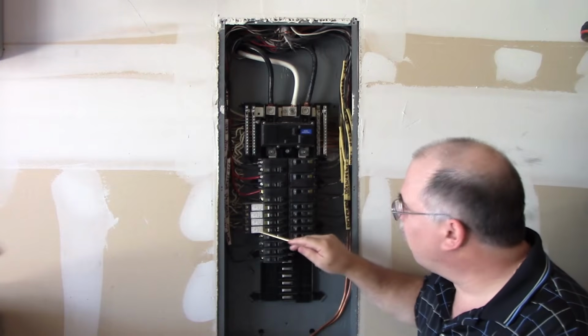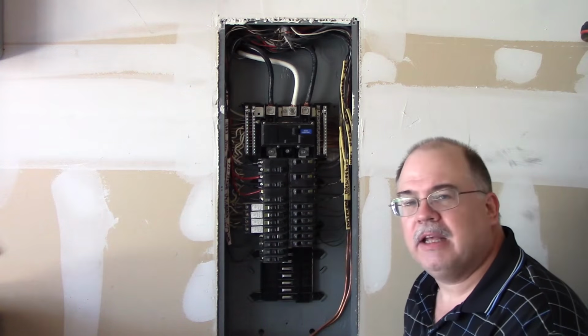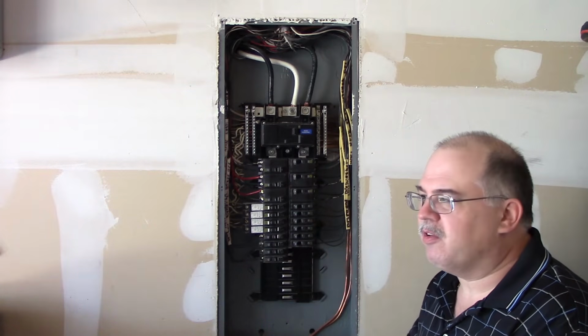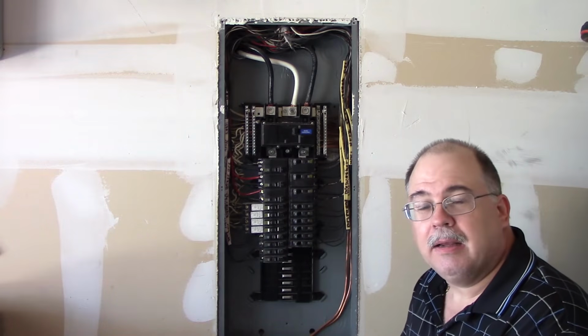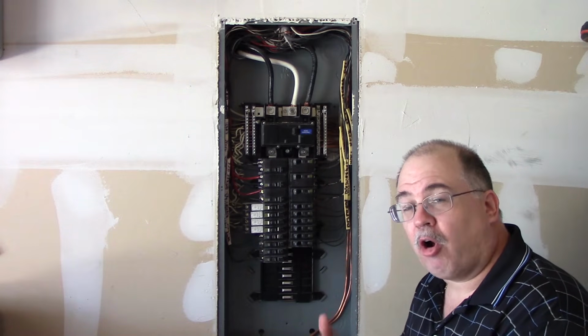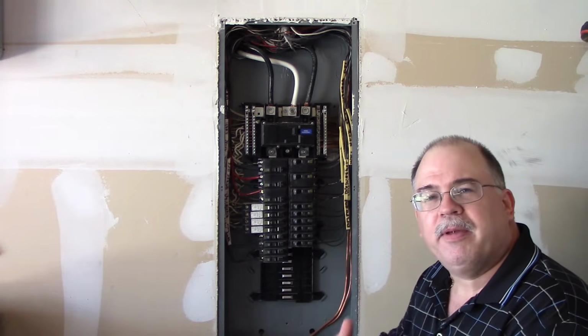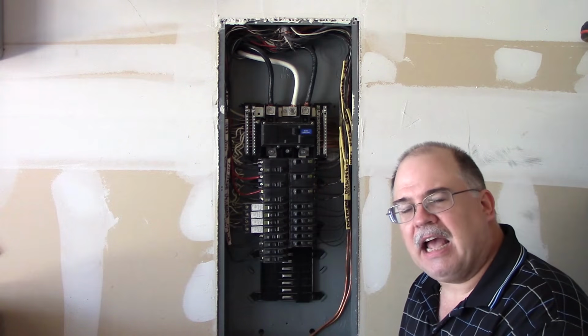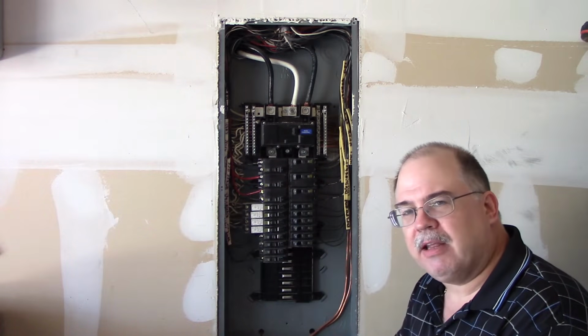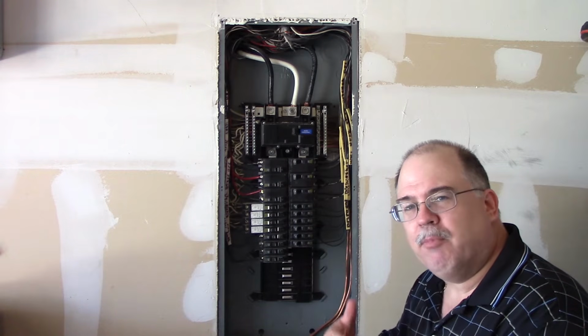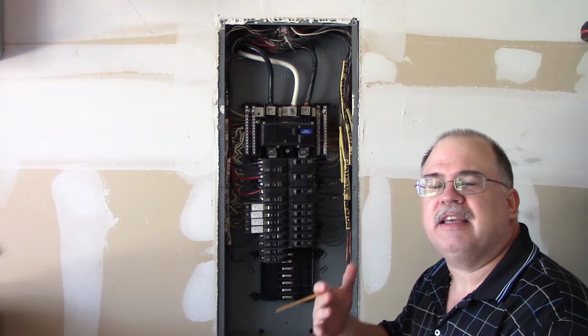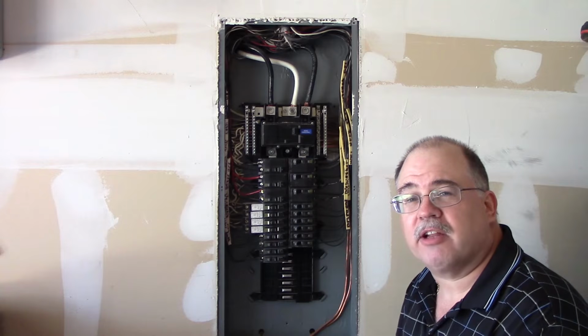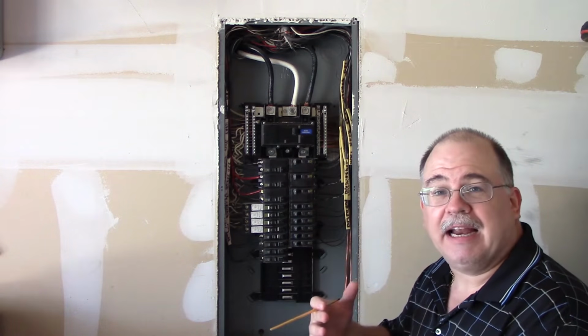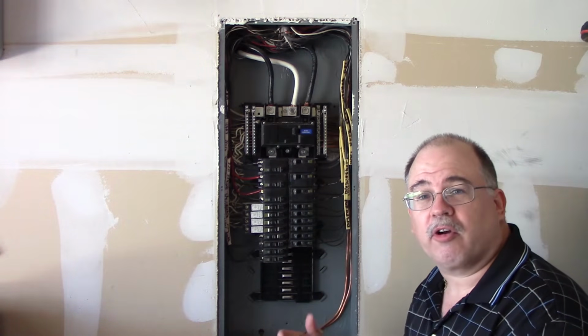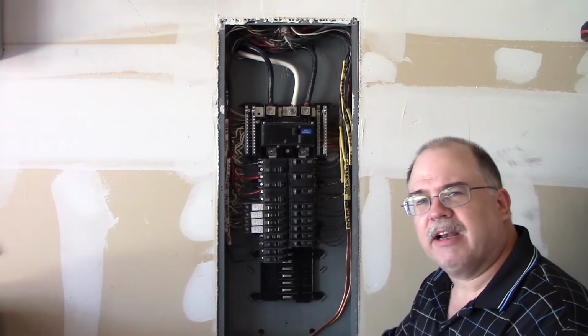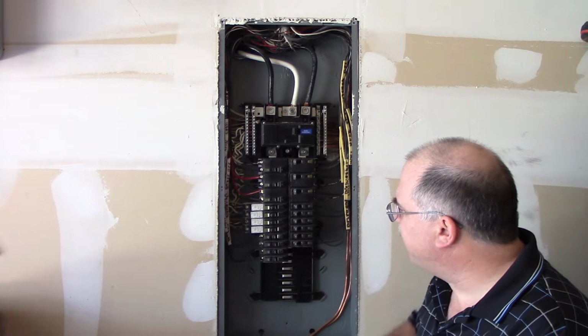These breakers right here are called AFCI breakers. This panel was installed in 2009, but AFCI breakers, that's arc fault circuit interrupters, have been around since 1999 requirements. Okay, it started out in the bedroom receptacles and it moved on to all the other outlets. And as you can see in 210.12(A) of the National Electrical Code, it has expanded greatly in the areas of the home that those circuits have to be protected for. So these happen to be a combination.